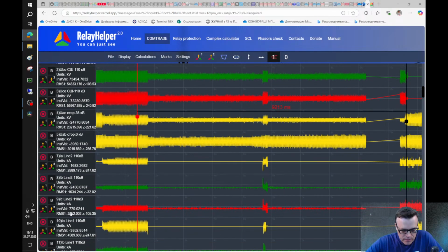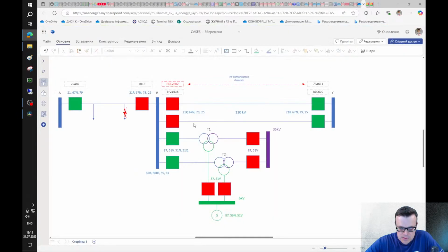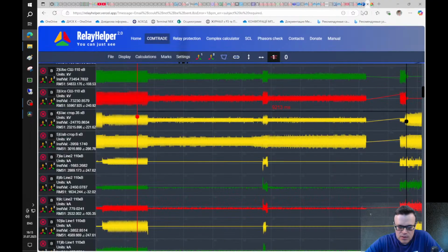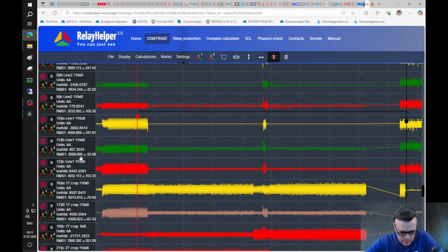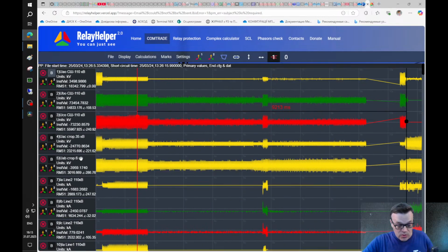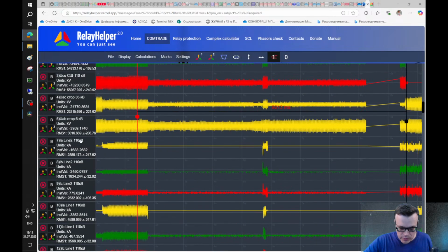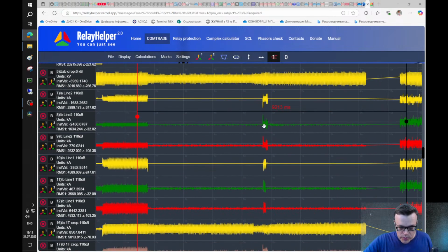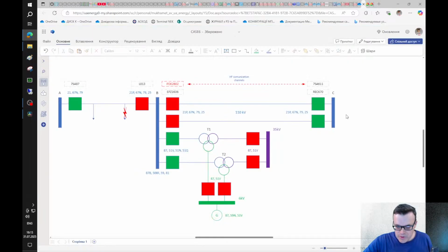The 5th channel is voltage between phase A, B from 6 kilovolt side. Here we have 3 currents from line 2. So this is this line. So line 1, line 2, and this one we don't see because I already removed channels with noises. So we can see currents from these 2 parallel lines.